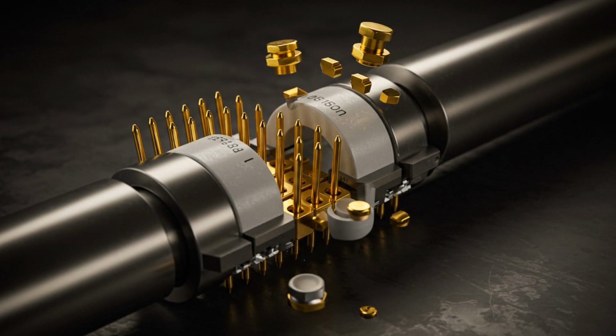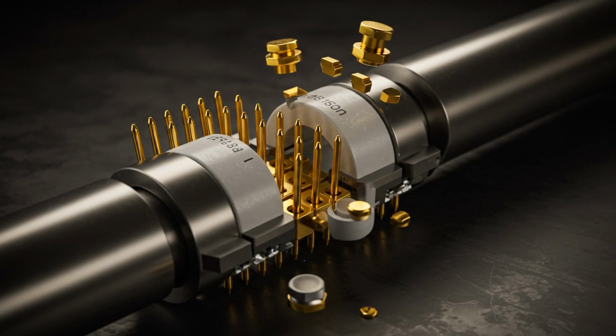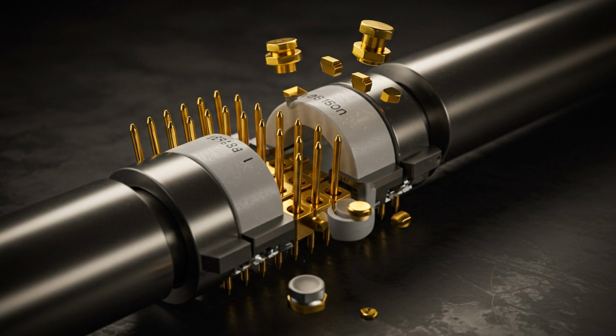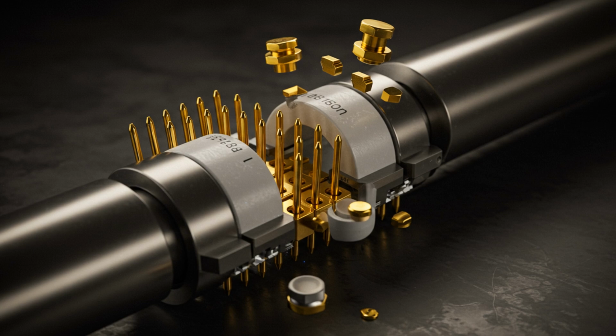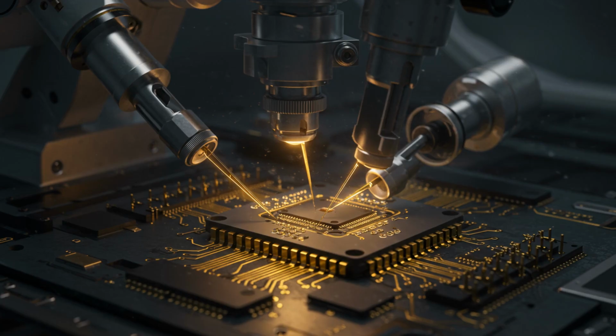This ceramic-to-metal bond must withstand the constant pulsing and temperature shifts of the human body without cracking. It is a bridge between two worlds, allowing the brain of the pacemaker to talk to the heart, while maintaining a wall that is essentially as solid as a single piece of stone. The precision here is measured in microns, ensuring the path for the electrical pulse is clear, but the path for moisture is forever blocked. Before the shell is closed, the brain must be installed.